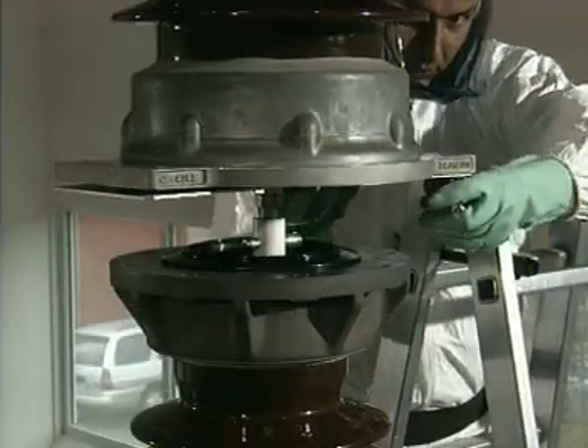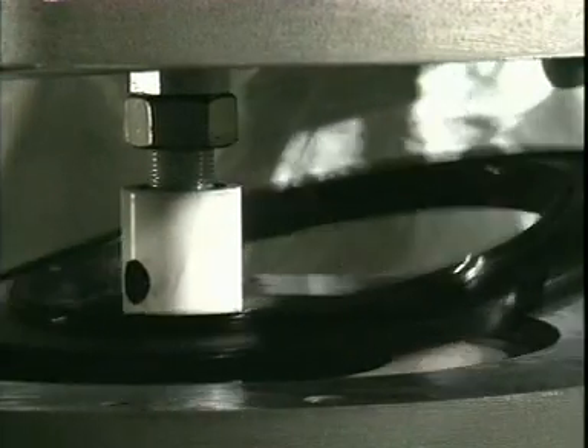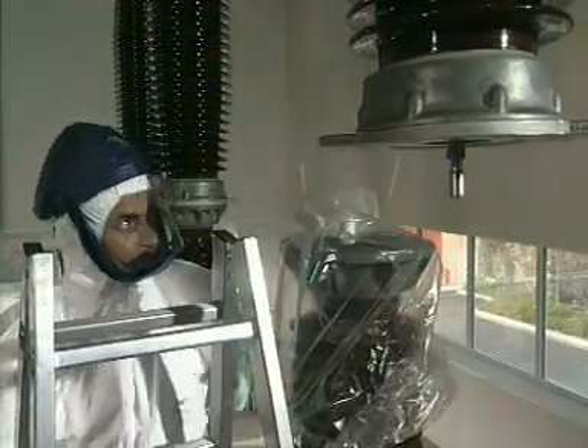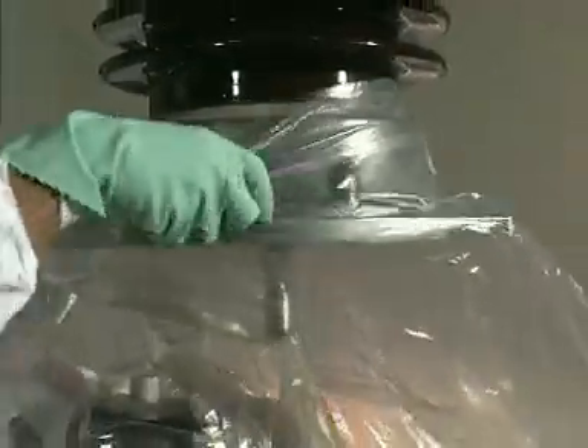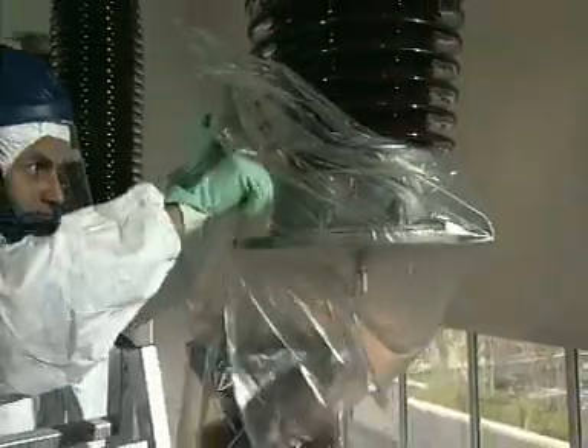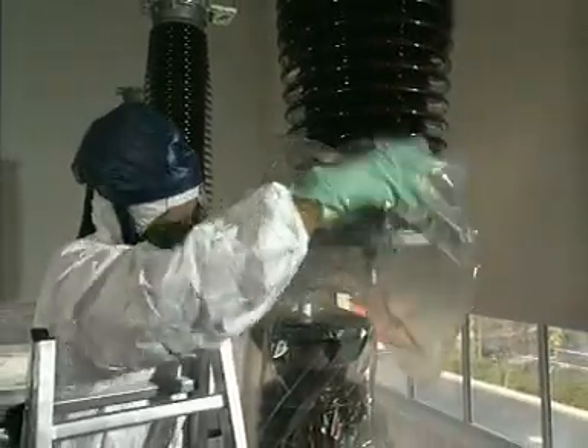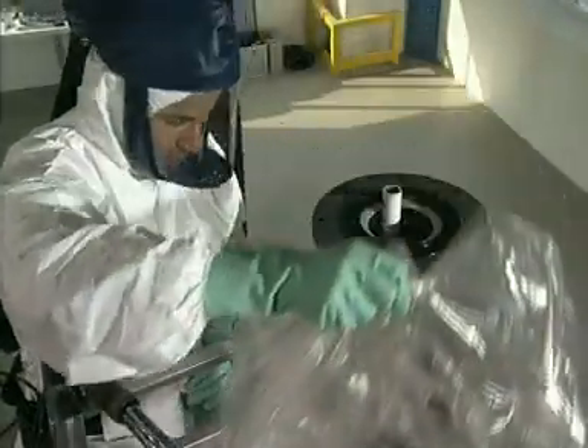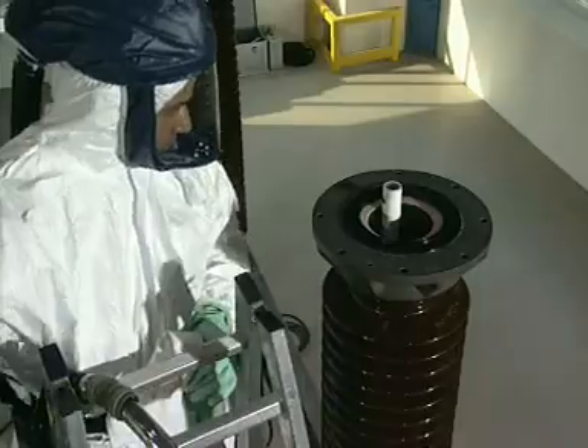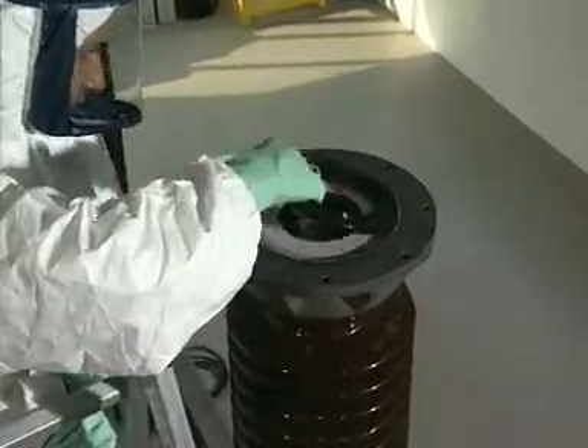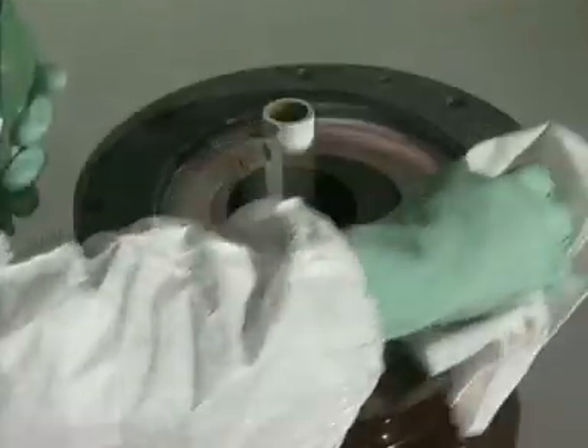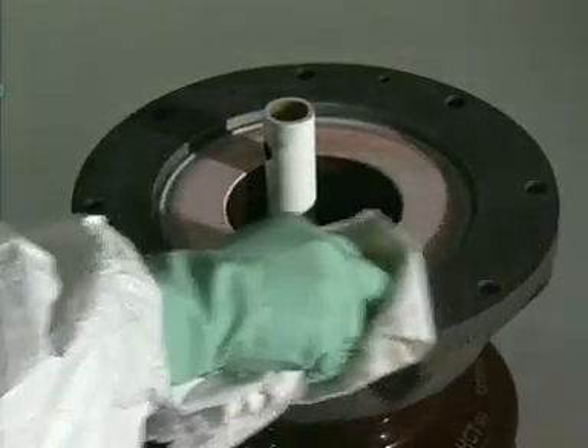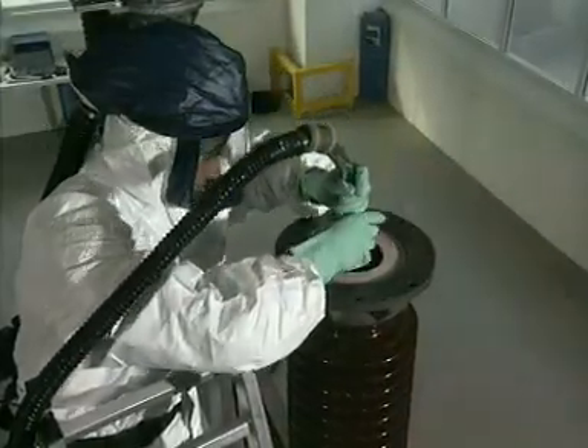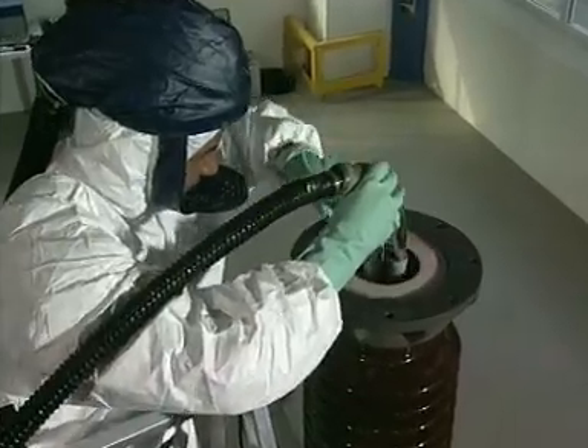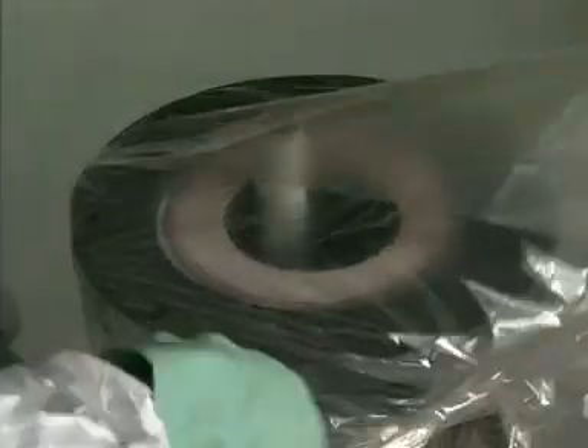Attach a coupling fixture and remove the coupling pin using a tool. Lift off the interrupter chamber and cover the open flange on the support porcelain so that it is dust tight. Wrap the interrupter chamber flange in dust-tight packaging and set it down on a suitable surface. Clean the sealing surface of the support porcelain using a rag and cleaning fluid. Clean the inside of the support porcelain using a vacuum cleaner and cover it again in a dust-tight manner.